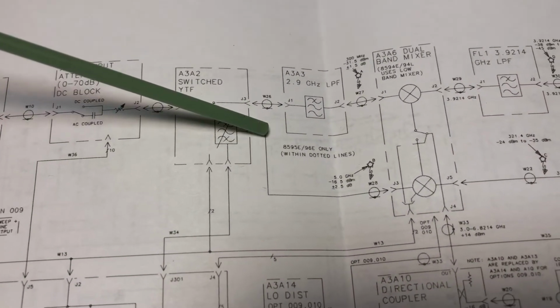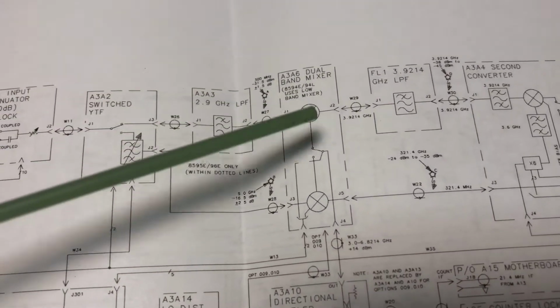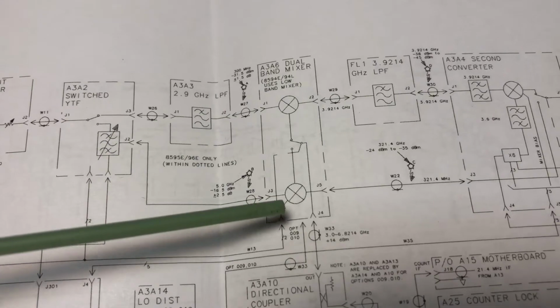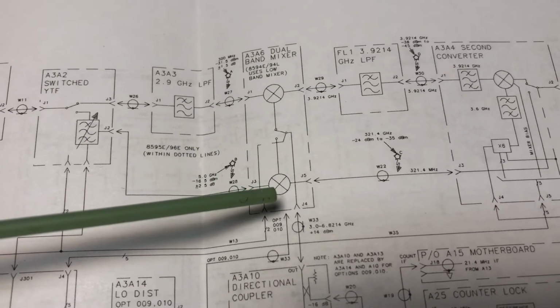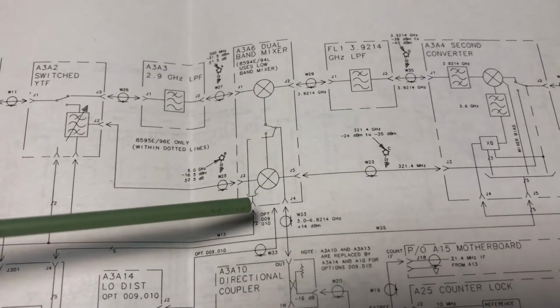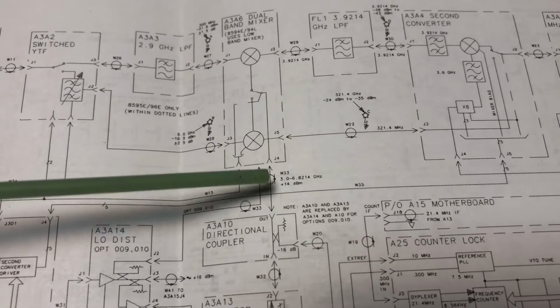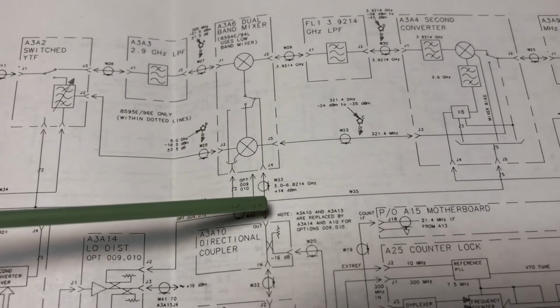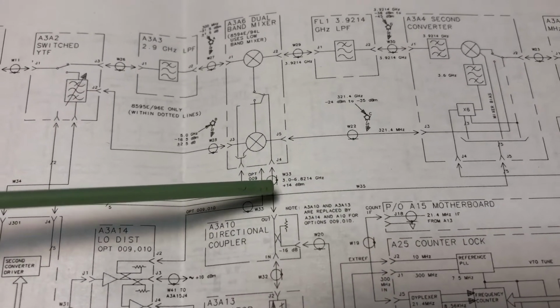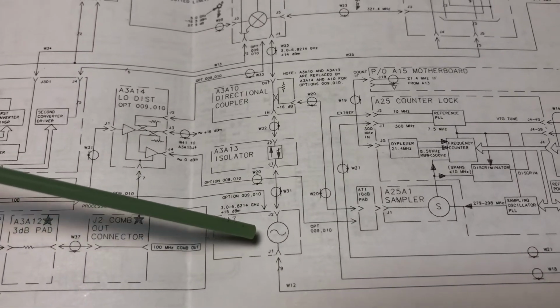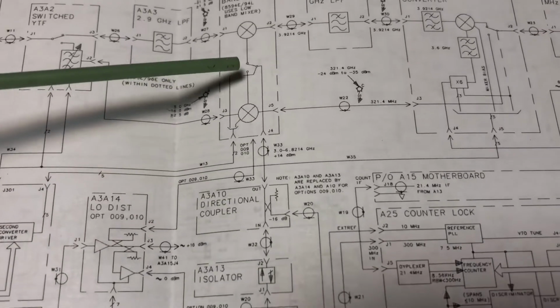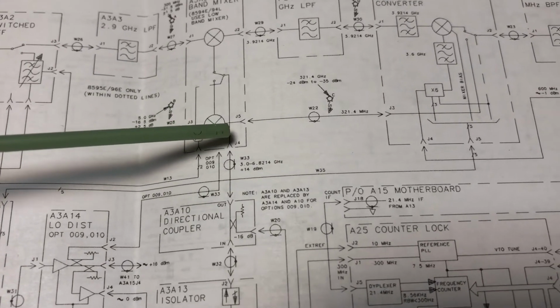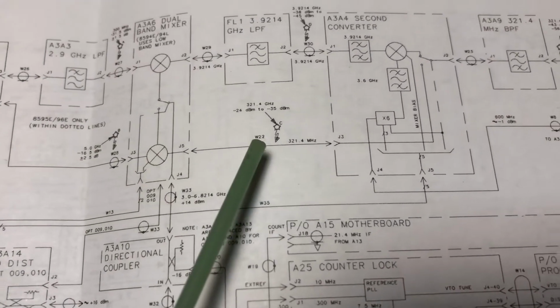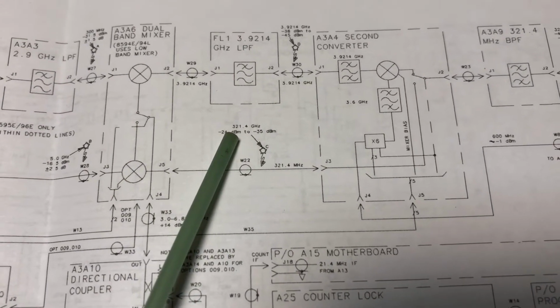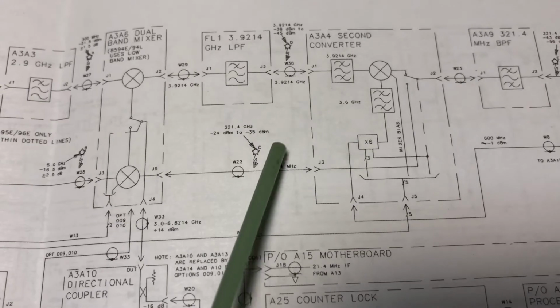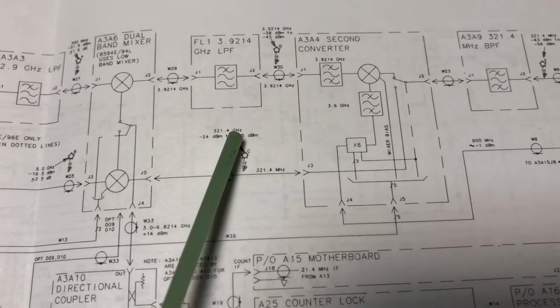From there, the output goes to a dual band mixer, and on the high band, it's a down converter mixer. So what the mixer does is it mixes the incoming signal, the incoming RF, with the signal out from the YIG-tuned oscillator here, and the product that comes out of the mixer is, as I said, down converted to 321.4, and this says gigahertz, but that's a misprint. It should be 321.4 megahertz.